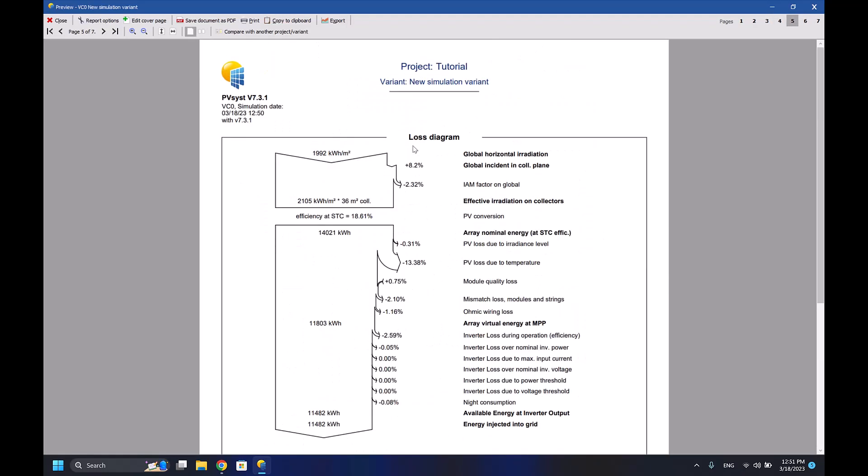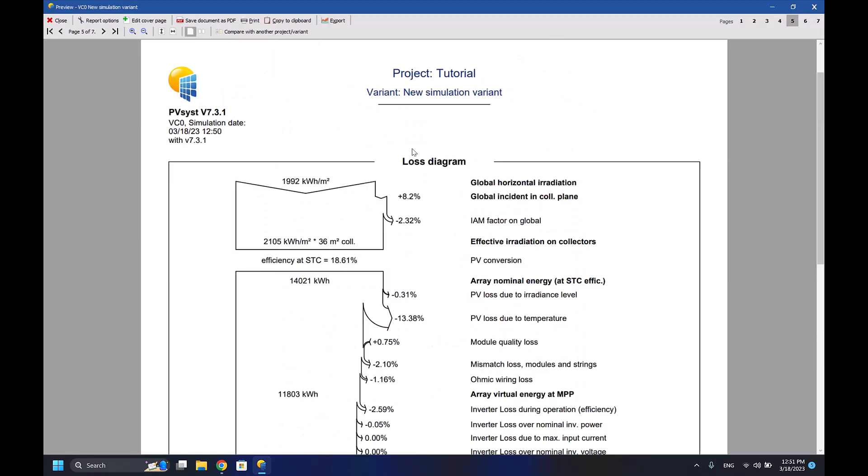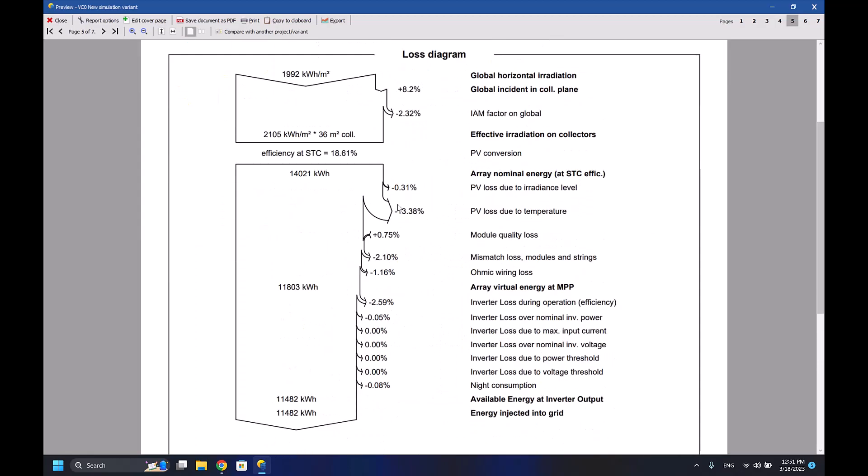The most important parameters are mentioned in this page - the main results - and also this page here which shows the losses diagram. For example, here we have 13.38% due to temperature losses because we are in the UAE which is a hot country in summer, so 13.38 percent losses from the temperature.